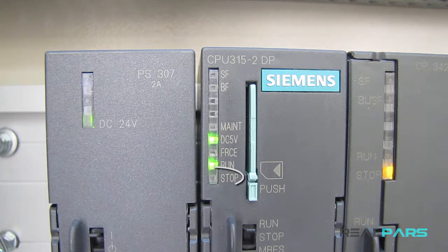And finally, the last LED light that we have on the CPU is the Stop red LED light. This light turns on whenever we either manually bring the CPU to a stop mode by means of a selector that's on the CPU, or due to a software or hardware error, the CPU is not able to run its program and hence it gets into a stop mode. So whenever you see that this LED light is on, the reason could be that it has been brought to a stop mode manually by means of a selector key, or it could be due to a problem in the CPU, and it has been brought to a stop mode automatically.